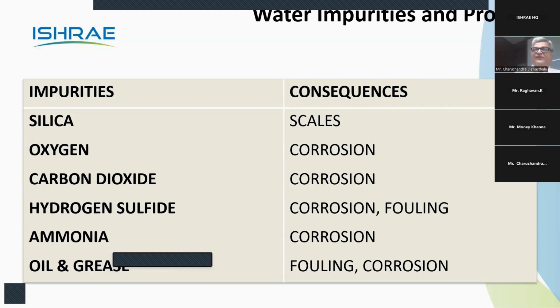Very high amount. It means a small amount of oil and grease in water can create havoc. I remember I was giving one training program to a Philippine company, and I was talking about all these water related issues. The owner said, you should talk more about oil and grease, because in our case oil and grease in the water is comparatively very low. In his case, oil and grease was so high that he said my entire cooling tower has collapsed twice because of fouling and generation of algae.